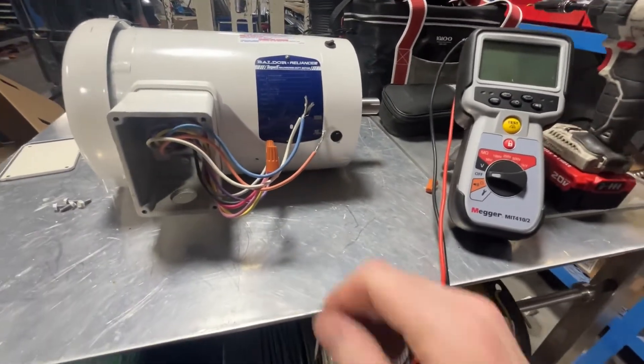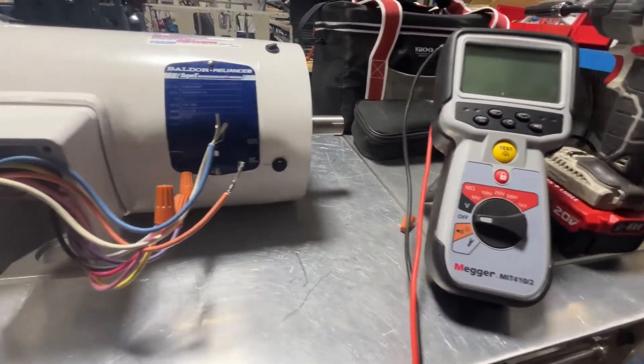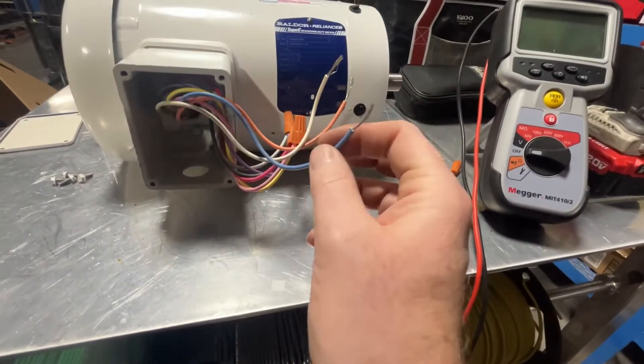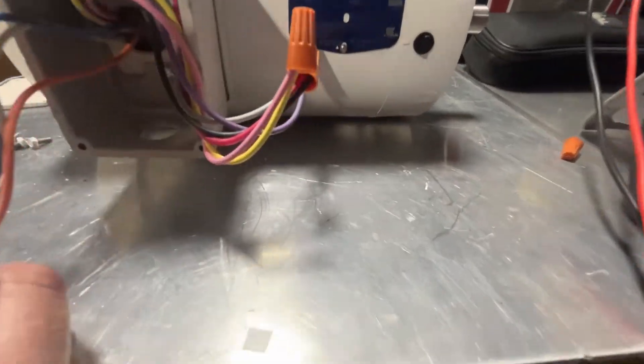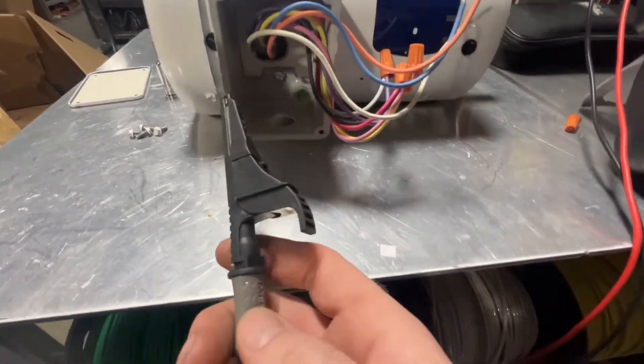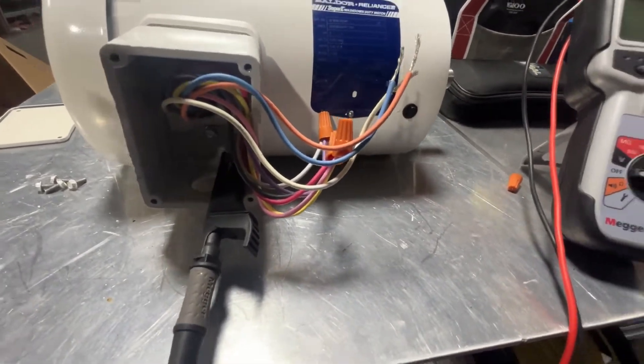Here we have a new Baldor motor — I think this is a one-and-a-half horsepower motor — and we're going to be megging it out to compare the difference between the new and the old. We're going to put the meter on continuity and read these leads to ground, starting with the blue, white, and orange — wires one, two, and three. This motor is wired for high voltage right now. I backed off the green ground screw a little bit to get a better bite with the black lead of the megger.